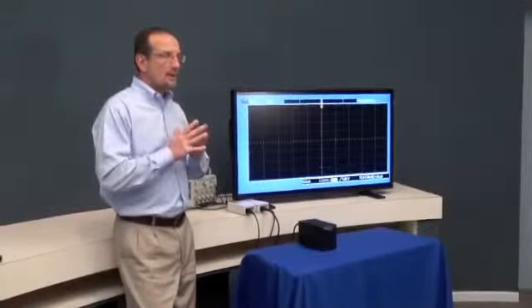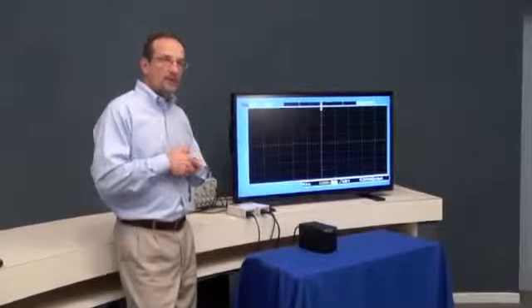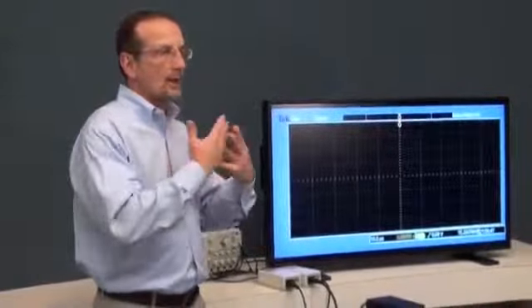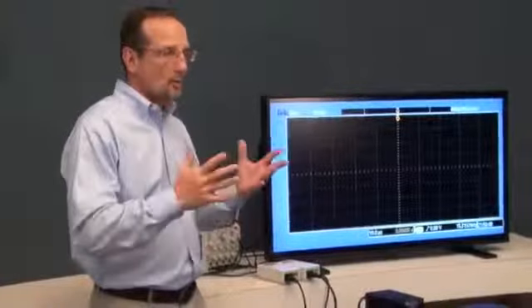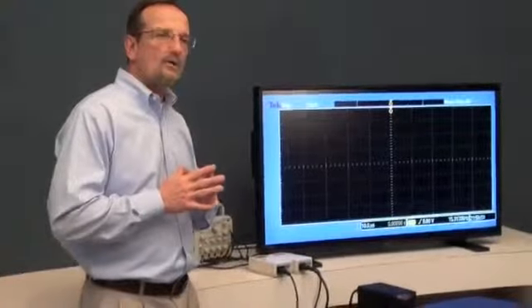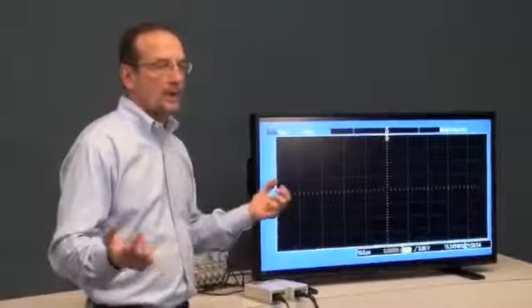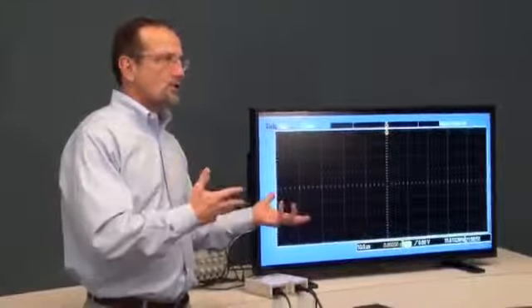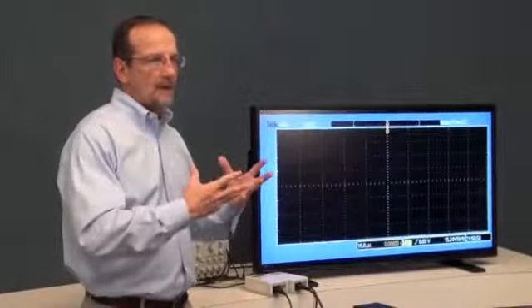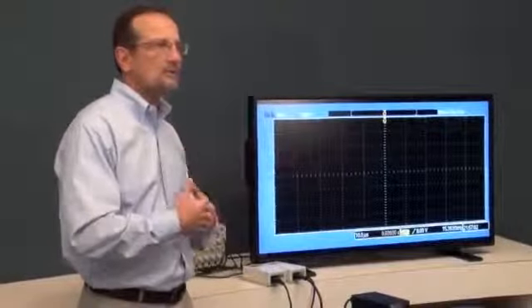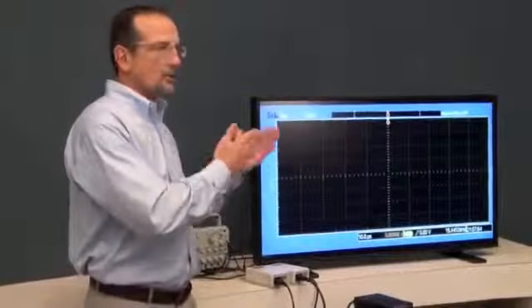Noise can be generated outside the building, for instance with lightning strikes or someone hits a power line or power lines being knocked down by storms. Or also we can have noise disturbances inside the building which can be caused by motor brushes that are dirty or relay contacts on an elevator or compressors kicking on and off in a refrigeration system, things like that that throw spikes of noise on the line.